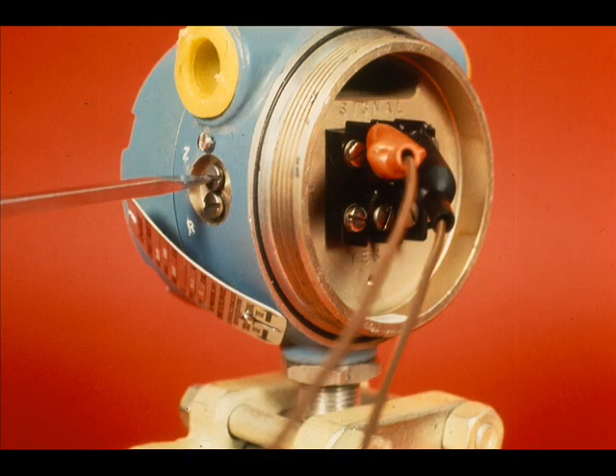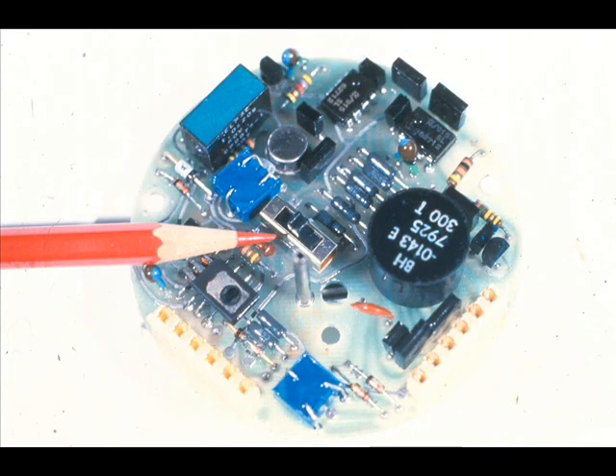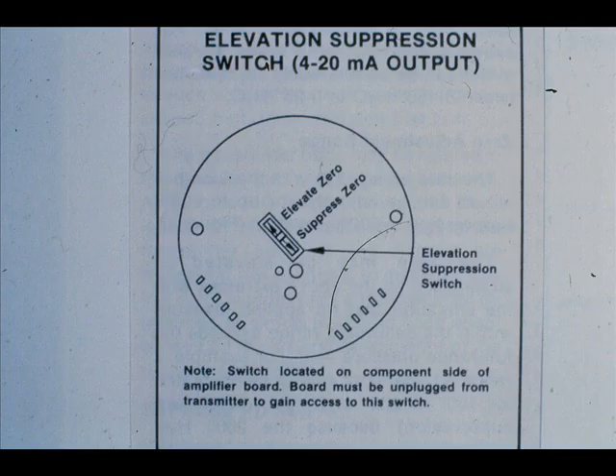The zero can be elevated or suppressed by turning the zero adjustment — check the instruction book for elevation and suppression limitations. Newer transmitters for the 4 to 20 milliamp systems have a three-position elevation/suppression switch on the amplifier board. The middle position allows normal amounts of elevation or suppression; to achieve large elevations or suppressions, move the switch to the elevate zero or suppress zero position.